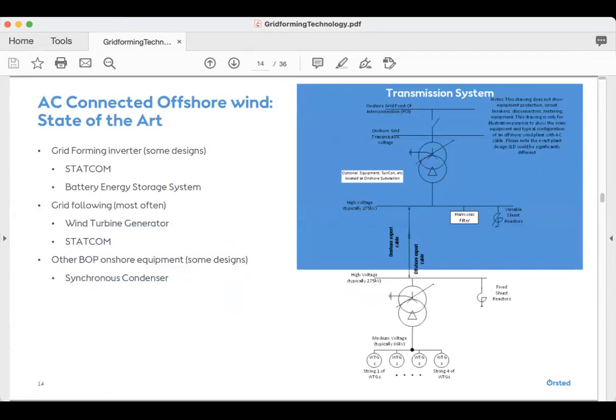So if you look at AC connected offshore wind, the state of the art today, we do use grid forming inverters. And again, by grid forming, I just mean those that can instantaneously control AC voltage and frequency. So in some designs, we've had grid forming STATCOMs on the onshore end. Again, a STATCOM is a balance of plant equipment for our AC designs, where we are using it just to maintain the reactive power requirements at the POI, or the point of interconnection.